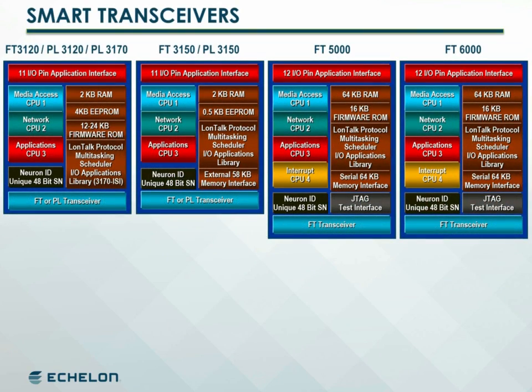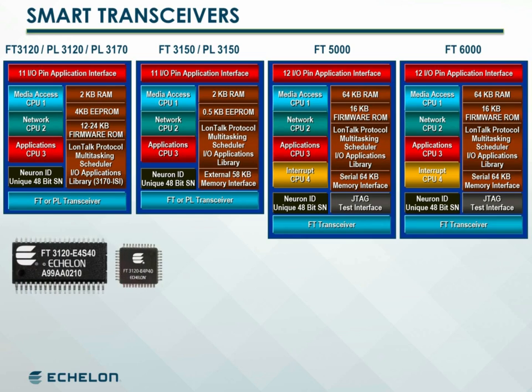To help device manufacturers reduce cost and simplify design, Echelon developed a smart transceiver. Smart transceivers integrate a transceiver — either a free topology twisted pair or a power line — with a Neuron core into a single chip solution.